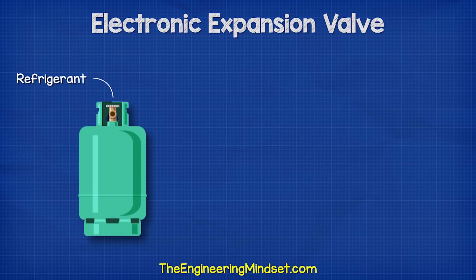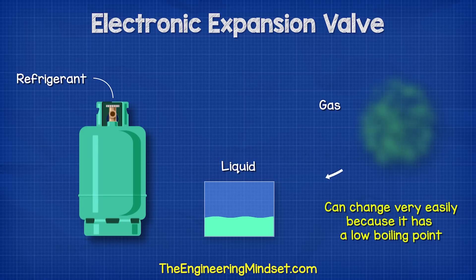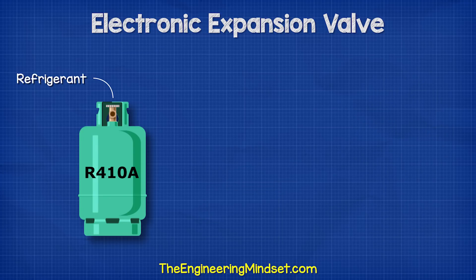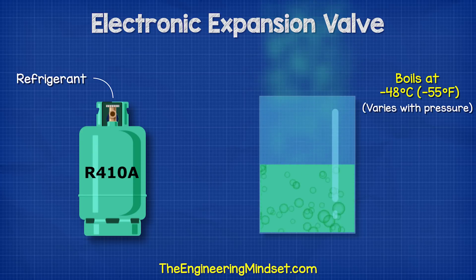The refrigerant is a specially designed fluid which can change between being a liquid and a gas very easily, and that's because it has a very low boiling point. For example, refrigerant R410A will boil at negative 48 degrees Celsius or negative 55 degrees Fahrenheit, although this will change with pressure.